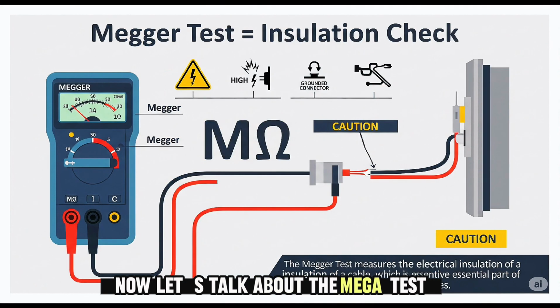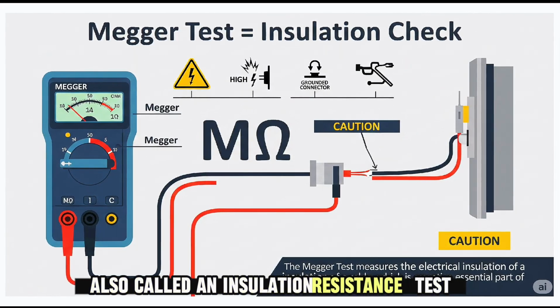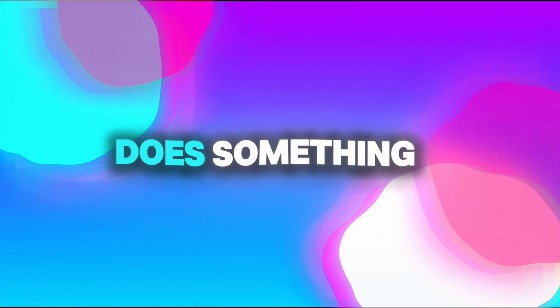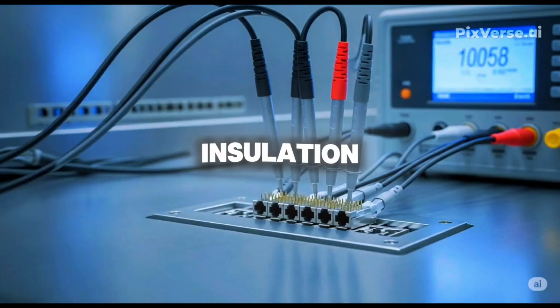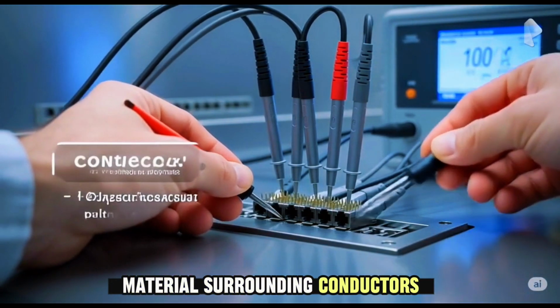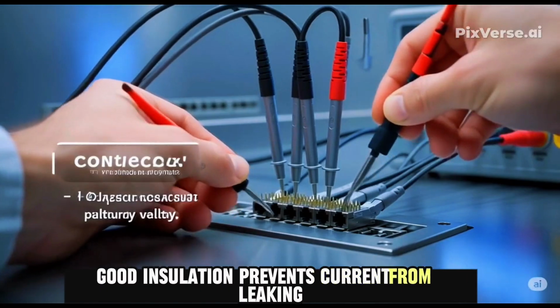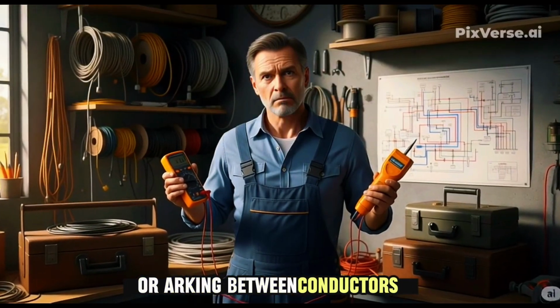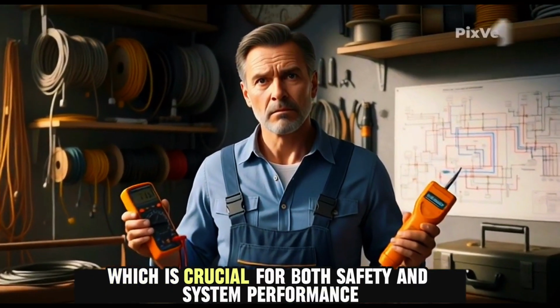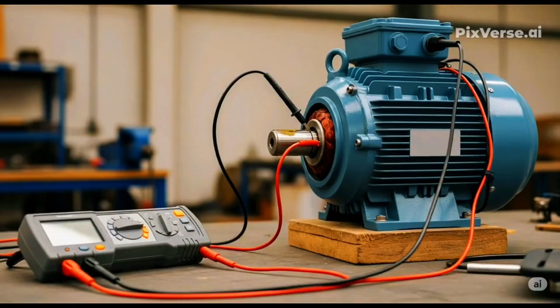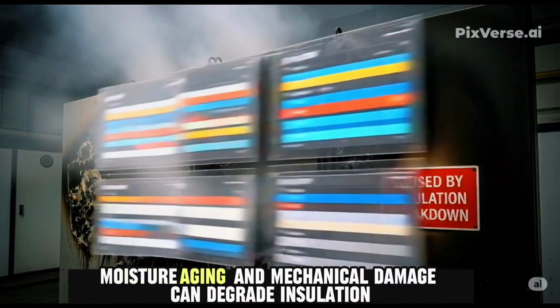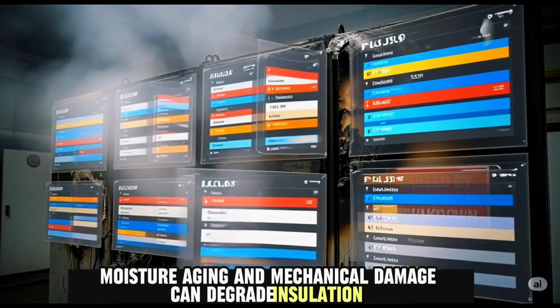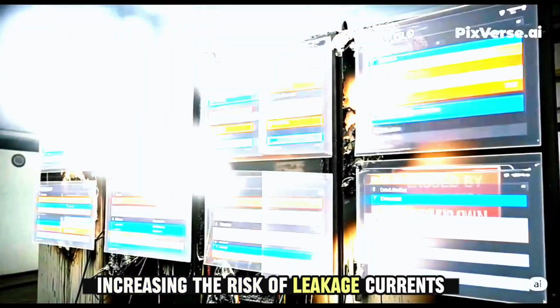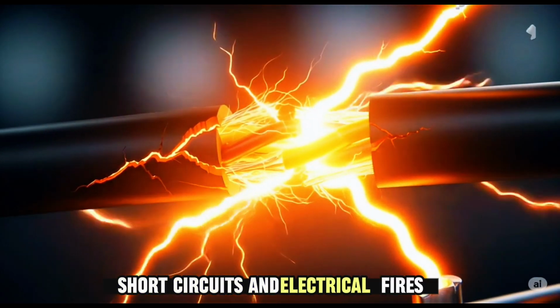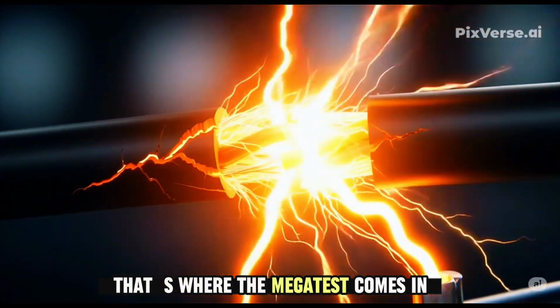Now let's talk about the Megger test, also called an insulation resistance test. This test does something completely different. It evaluates the quality and integrity of the insulation material surrounding conductors. Good insulation prevents current from leaking or arcing between conductors or to the ground, which is crucial for both safety and system performance. Over time, heat, moisture, aging, and mechanical damage can degrade insulation, increasing the risk of leakage currents, short circuits, and electrical fires. That's where the Megger test comes in.